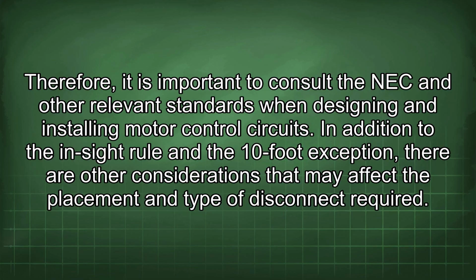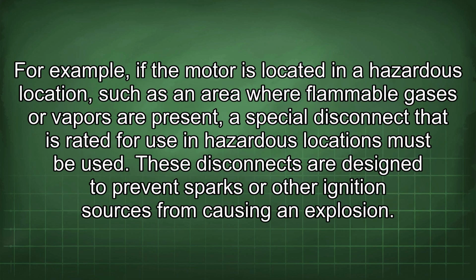In addition to the in-sight rule and the 10-foot exception, there are other considerations that may affect the placement and type of disconnect required. For example, if the motor is located in a hazardous location, such as an area where flammable gases or vapors are present, a special disconnect that is rated for use in hazardous locations must be used. These disconnects are designed to prevent sparks or other ignition sources from causing an explosion.